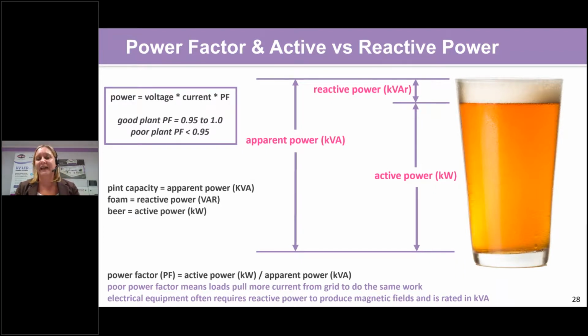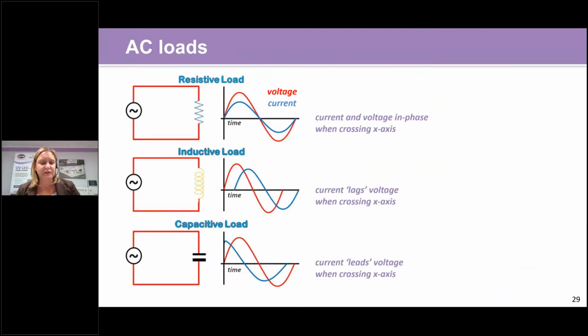kVA includes active power and reactive power. Just a couple quick slides left. AC loads, and again, another technical slide. I apologize to those of you who aren't technical, but this is important. Resistive loads, inductive loads, and capacitive loads are what you're going to see connected to an AC line. In an ideal world, the resistive load that you see on top, the voltage and the current are in phase. They cross the x-axis, which is time, at the same point in time.